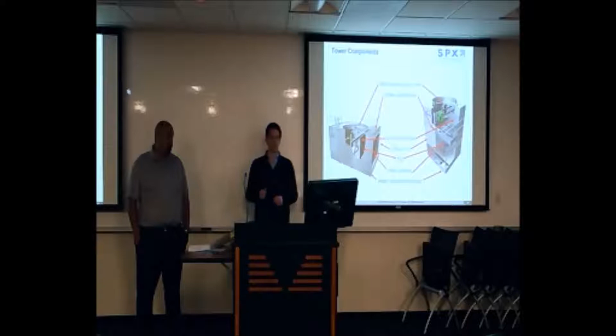If the buildup's kind of aggressive and hard to remove with the broom, you can get a pressure washer and put it on a very low setting to blast the louver face. If you put it on a high setting, you'll find that PVC film fill isn't very thick, so you'll end up tearing through some of that fill. So keep it on a very low pressure setting when cleaning the louvers that way.